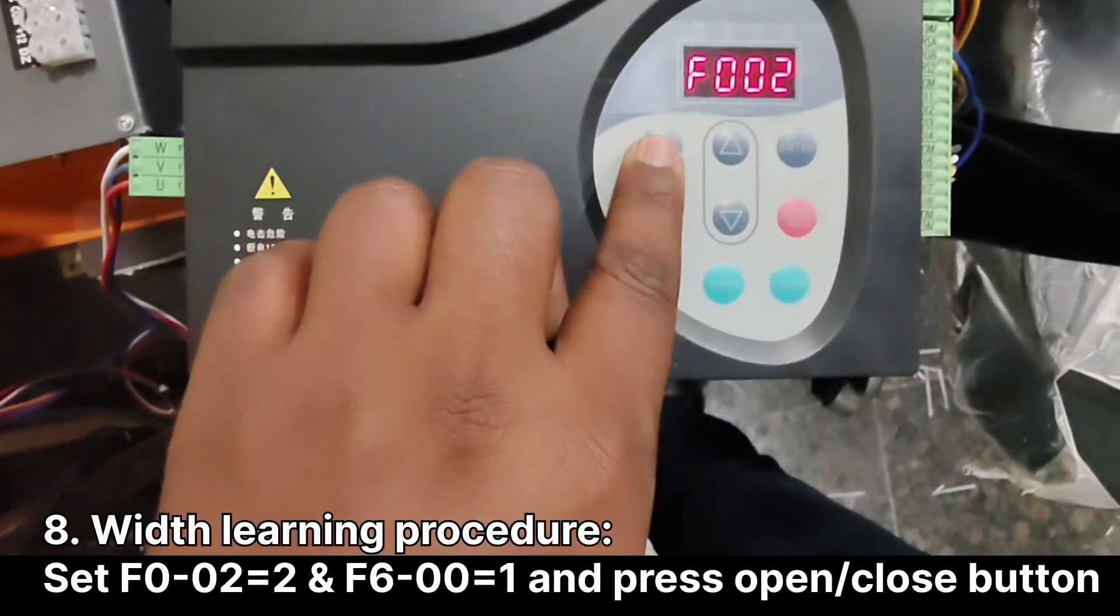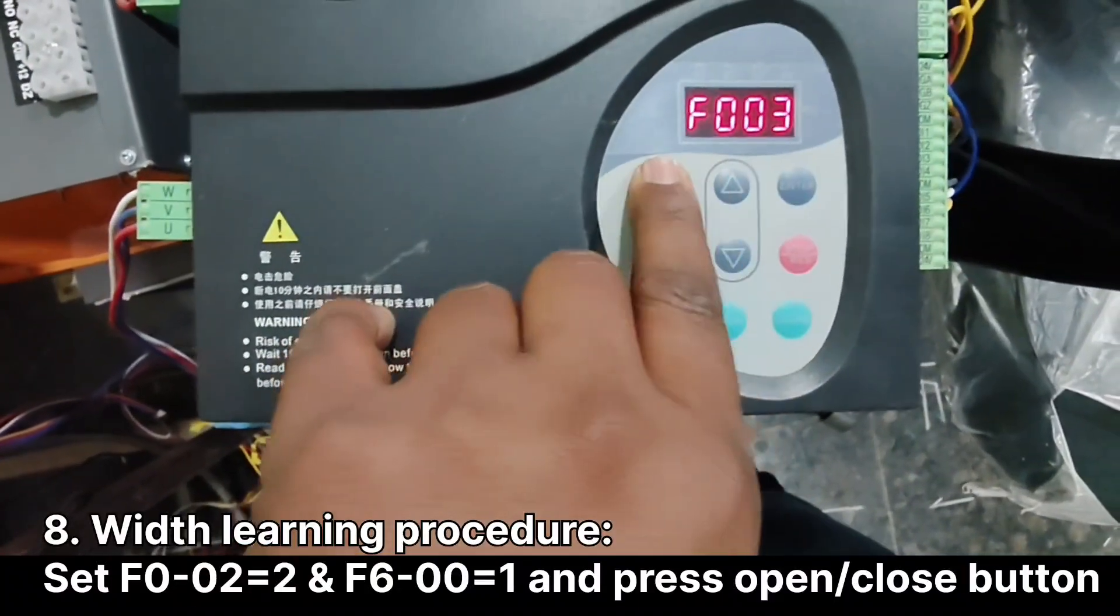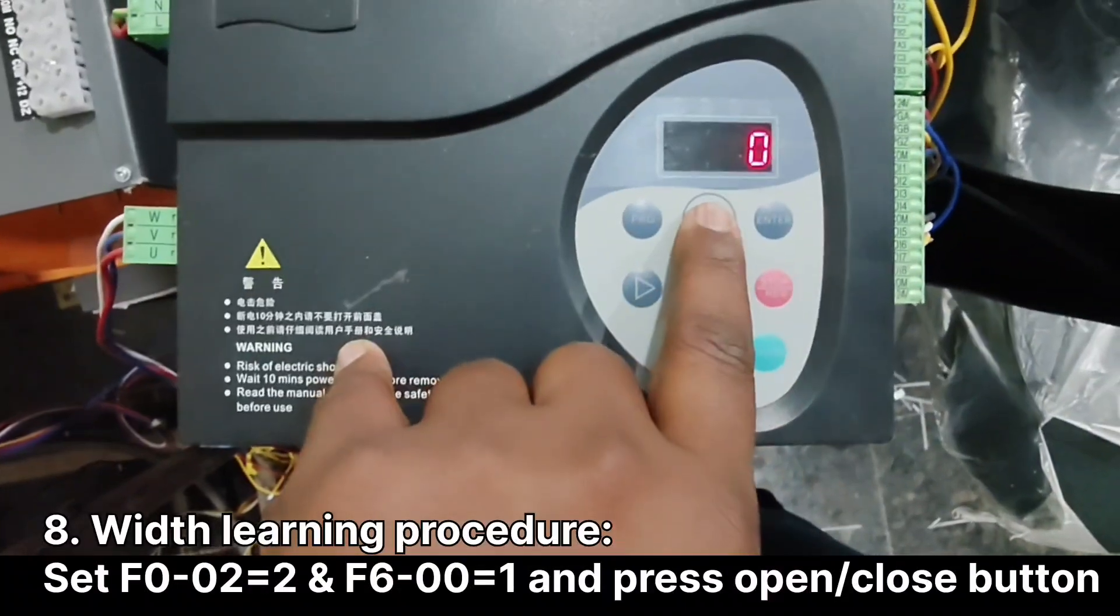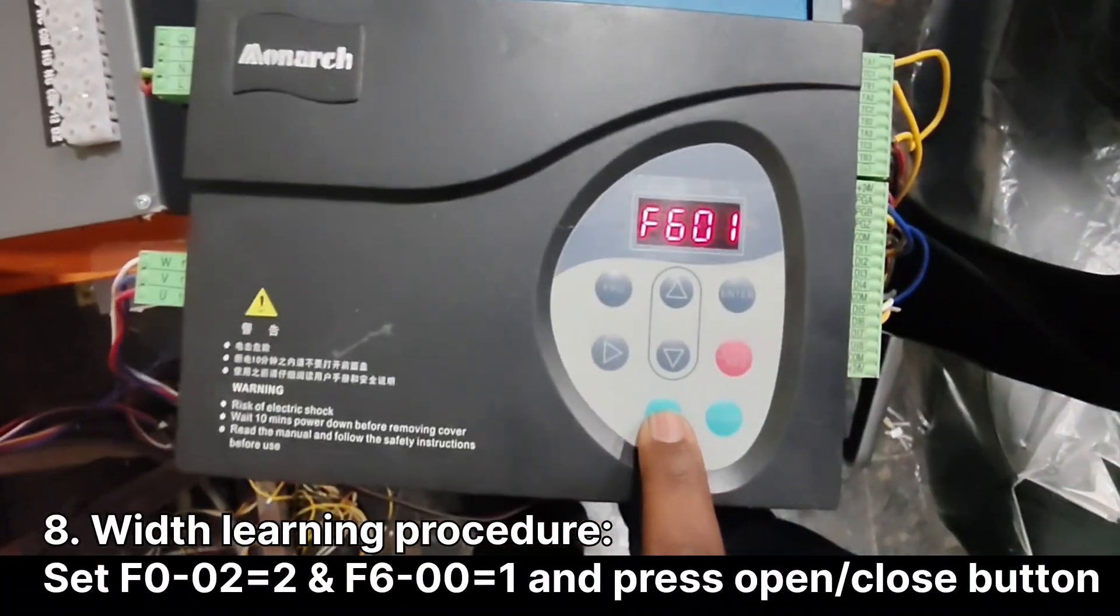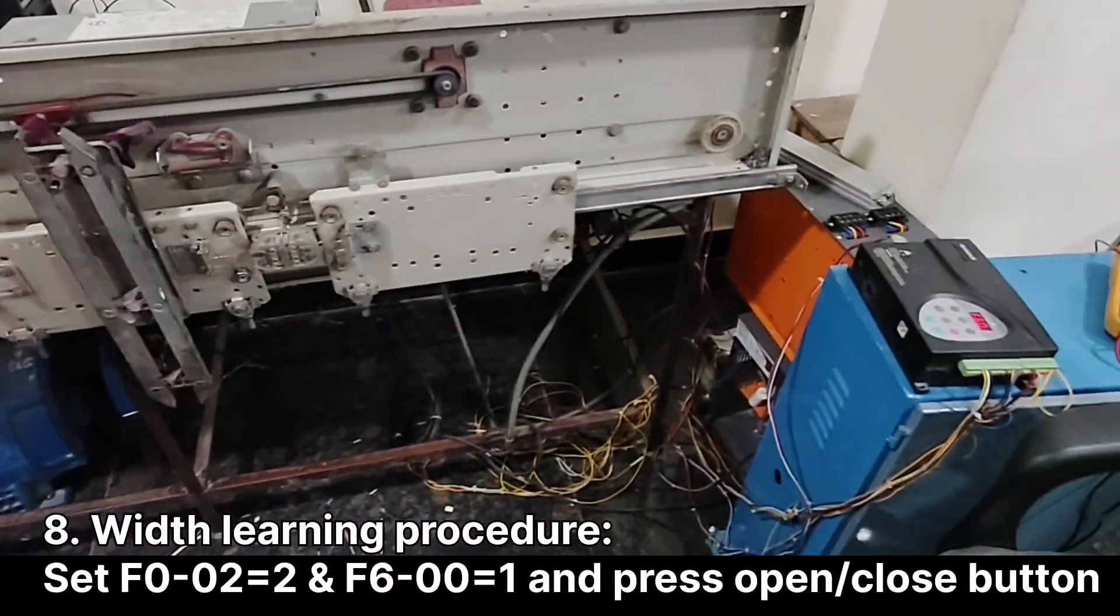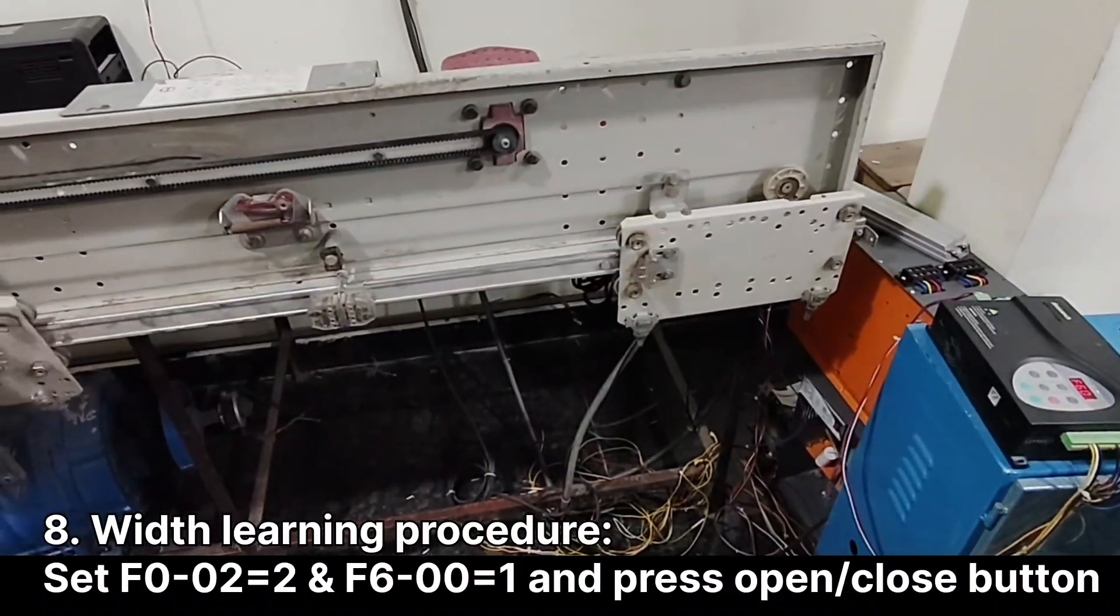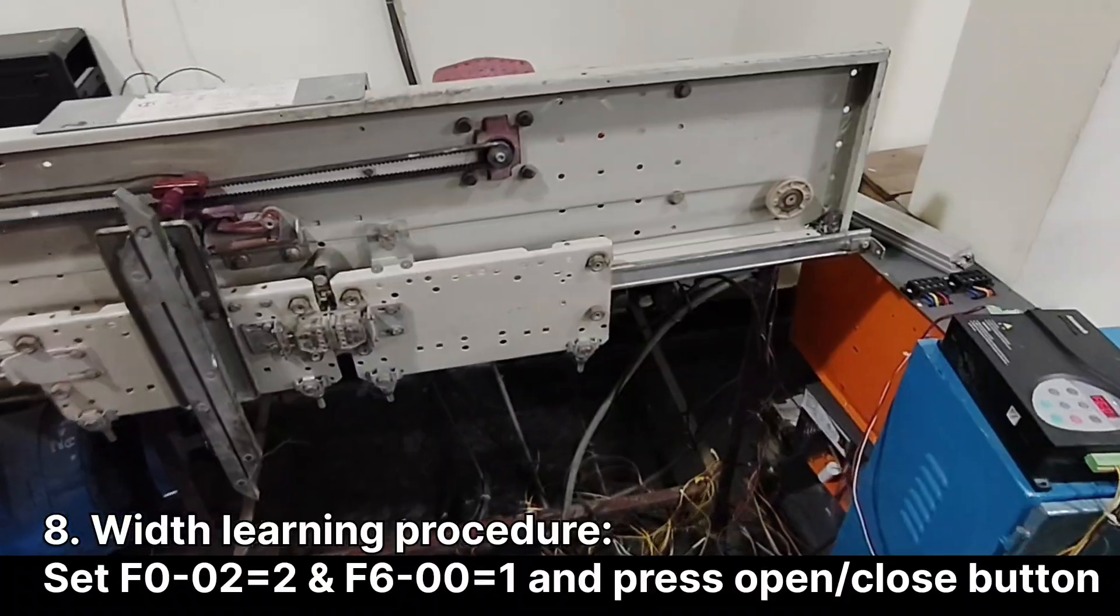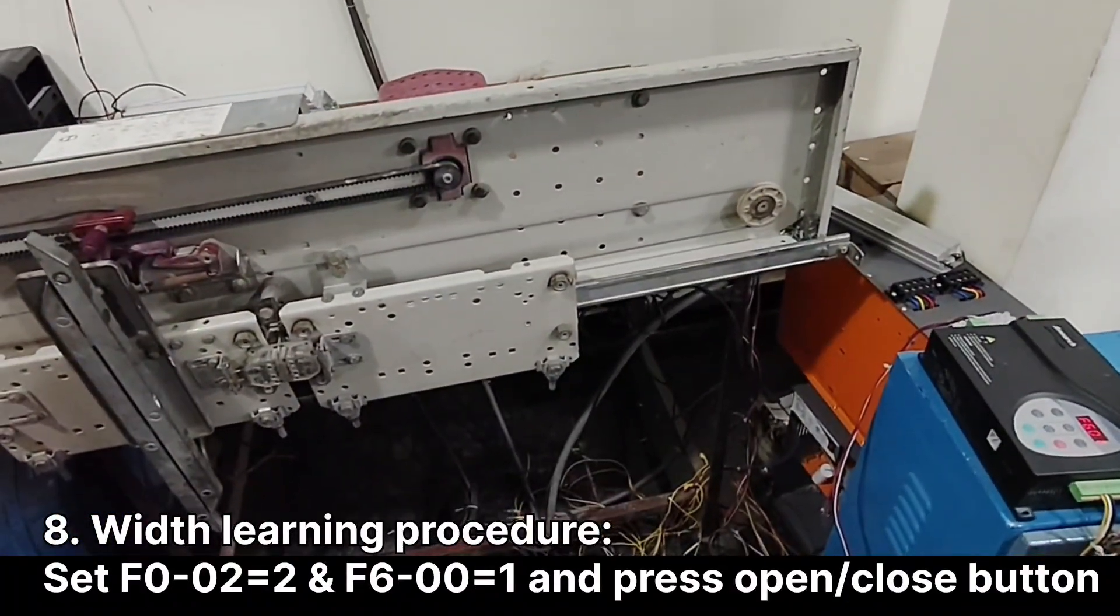For width learning, set F002 to 2 and F600 to 1. Give enter, then press open or close button. Door will open and close 3 times. After width learning is completed, LED will turn off.